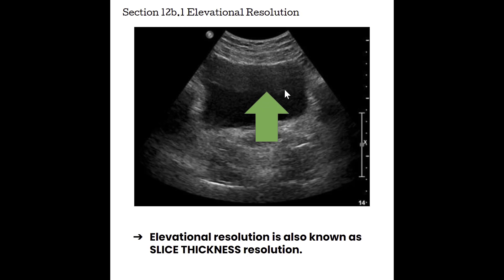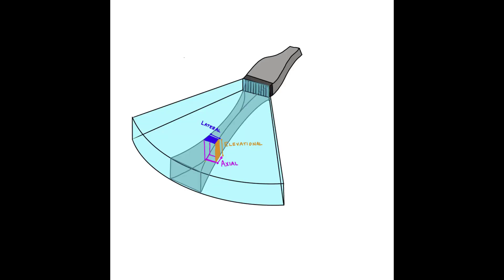Elevational resolution grabs echoes from other structures that sit above or below the main part of the beam. Because of this, it is also known as slice thickness resolution. Looking at all three resolutions: axial resolution is parallel with the sound beam, represented by the pink arrow. Lateral resolution is the side-to-side of the sound beam, concurrent with beam width, represented in blue. Elevational resolution is the height or thickness of the beam, represented in orange.